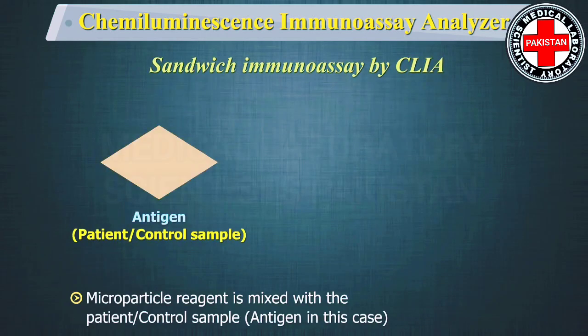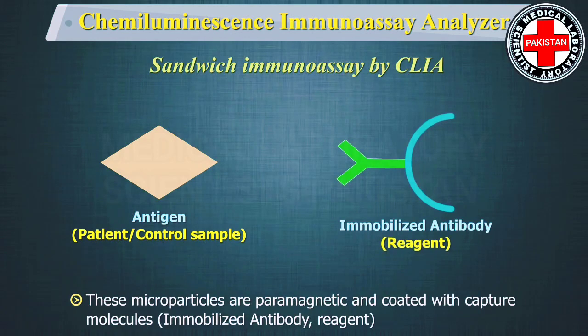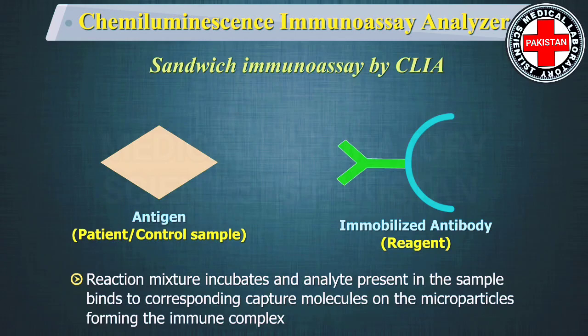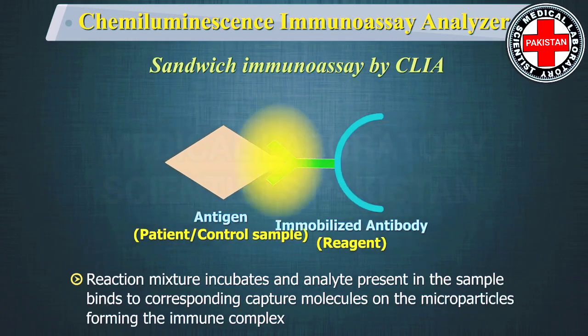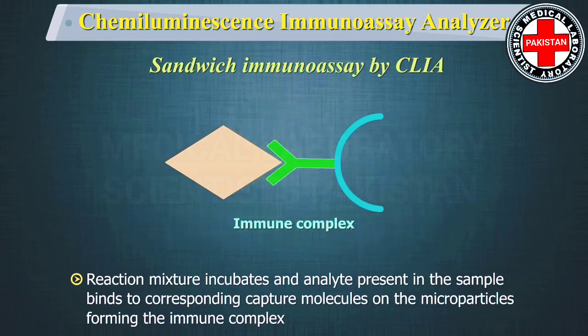The microparticle reagent is mixed with the patient or control sample. These microparticles are paramagnetic and coated with capture molecules. The reaction mixture incubates and the analyte present in the sample binds to the corresponding capture molecules on the microparticles, forming the immune complex.